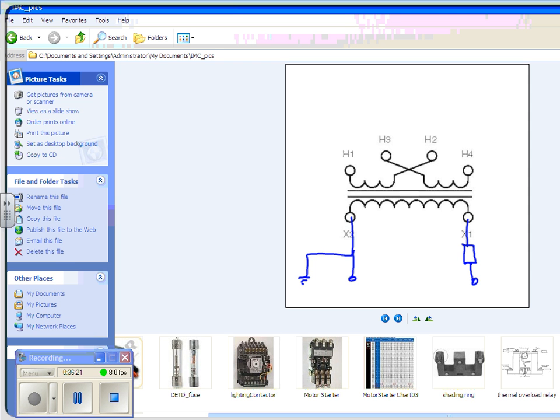One is called common control. That's where you take whatever voltage you have on line A and line B, and you use that to control your circuit. Your control circuit might be at 277, 480 if you do common control, right? How many people want to have 277, 480 on their control circuit? Even if it's fused so that you can only get a few amps. That's probably not going to be any fun if you touch it and you're touching something grounded. Probably not anybody's favorite. So that is going away in general as a control method.